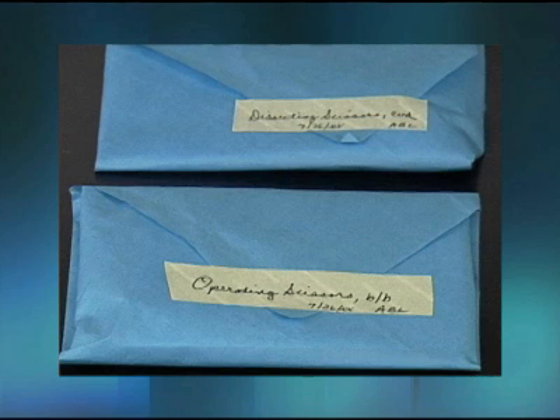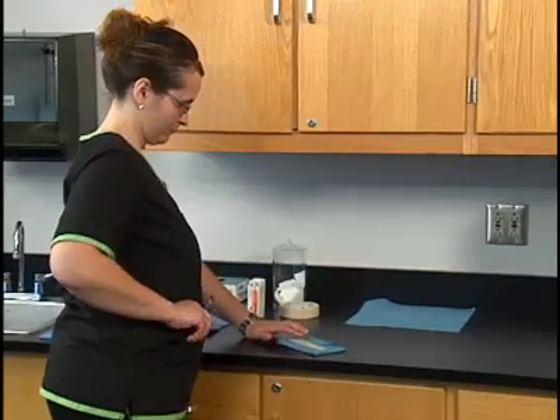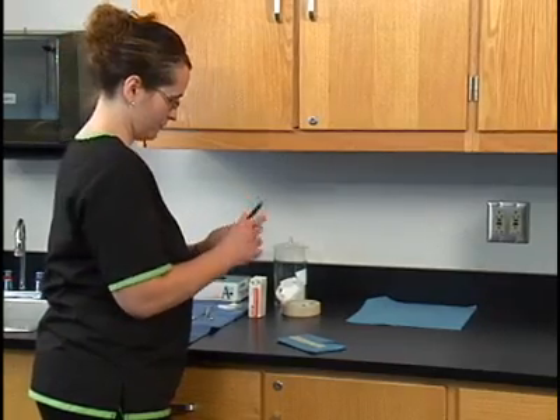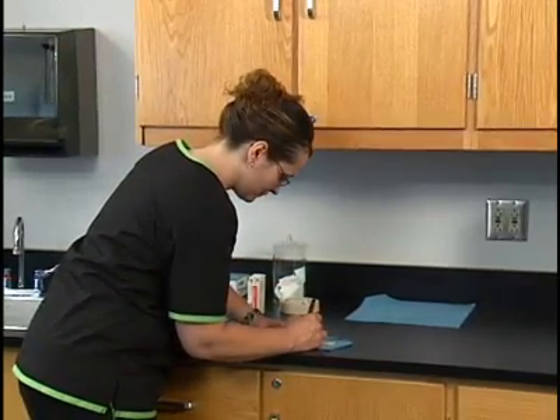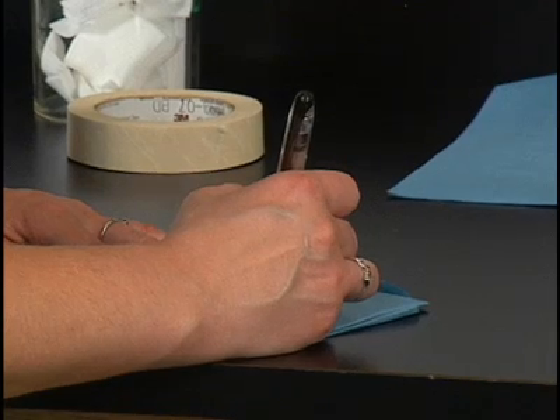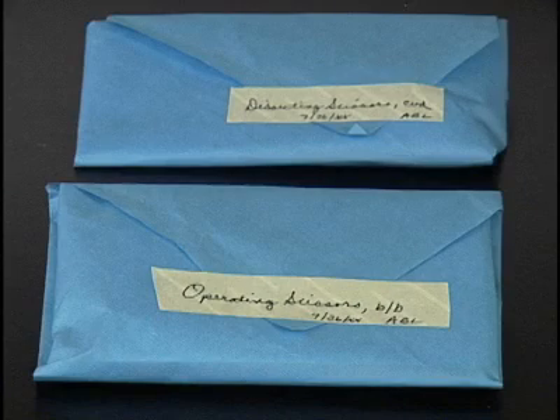Instruments must be wrapped properly to permit full penetration of steam and to prevent contaminating them when the wrap is opened. Label the pack according to its contents. Mark the pack with the date of the sterilization and your initials. Dating the pack ensures that the most recently sterilized packs are stored in back of previously sterilized packs.